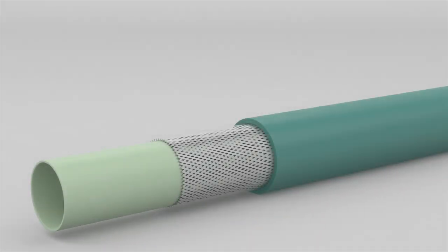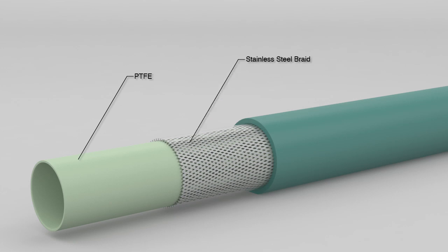Conventional guide catheter shafts are constructed with three distinct layers. A PTFE inner layer provides lubricity to facilitate device passage. A stainless steel braided layer enhances torque transmission and shaft support. A thermoplastic outer layer provides a smooth surface against the blood vessel wall.